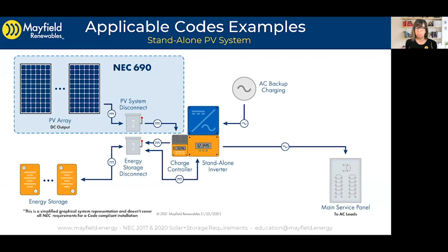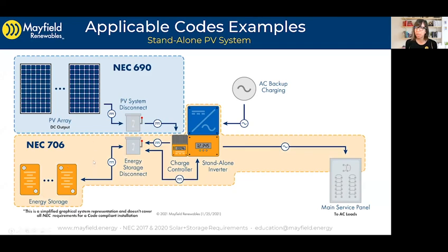With our standalone system, it's slightly less complicated because we don't have the utility to deal with, but all the same Article 706 sections still apply to the energy storage system — overcurrent protection, circuits, disconnects, and charge control requirements all still apply in the standalone setting as well. It doesn't matter what kind of energy storage system you have: if energy storage is involved, you need to apply all those sections from Article 706 to the appropriate circuits and components.